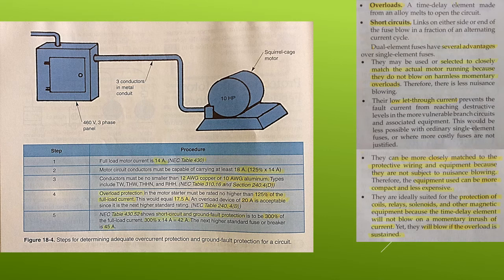Dual element fuses have several advantages over single element fuses. First, they may be selected to closely match the actual motor running current because they do not blow on harmless momentary overloads. Therefore, it is less of a nuisance blowing. And their low let-through current prevents fault current from reaching destructive levels in the more vulnerable branch circuits and associated equipment. This would be less possible with ordinary single element fuses or where more costly fuses are not justified.